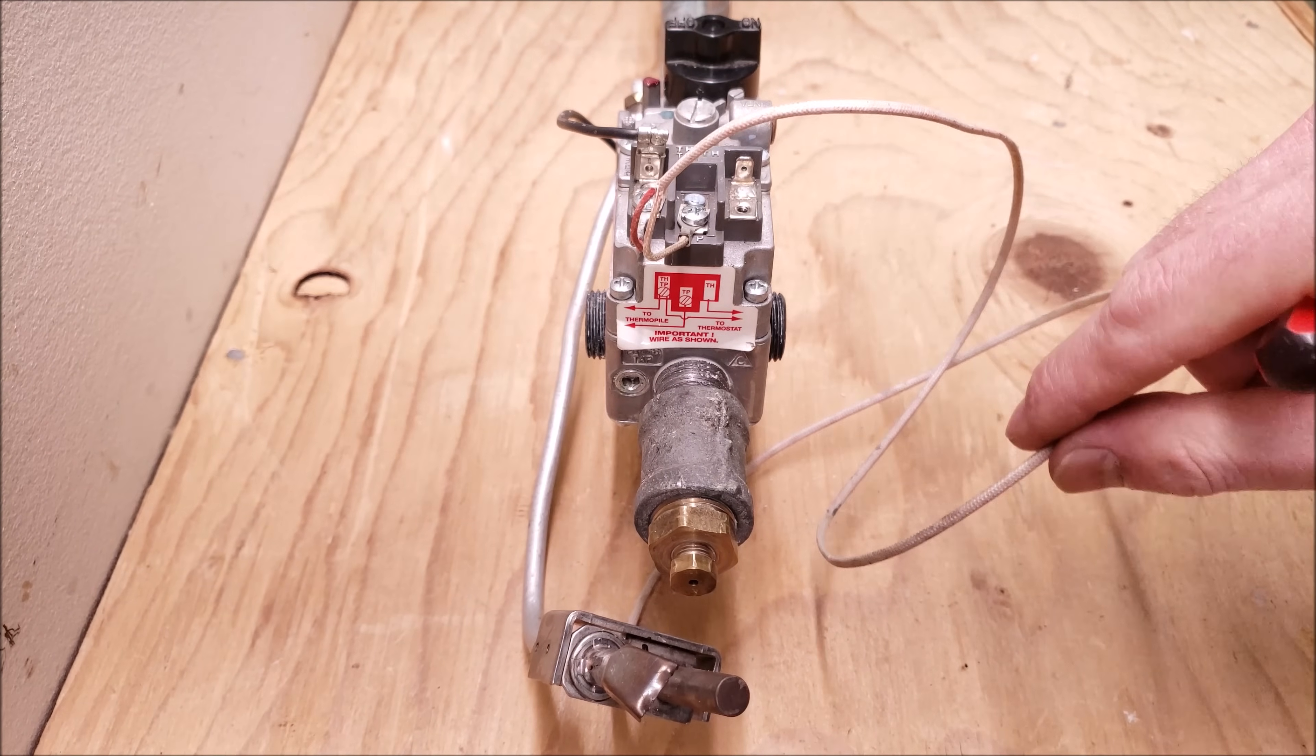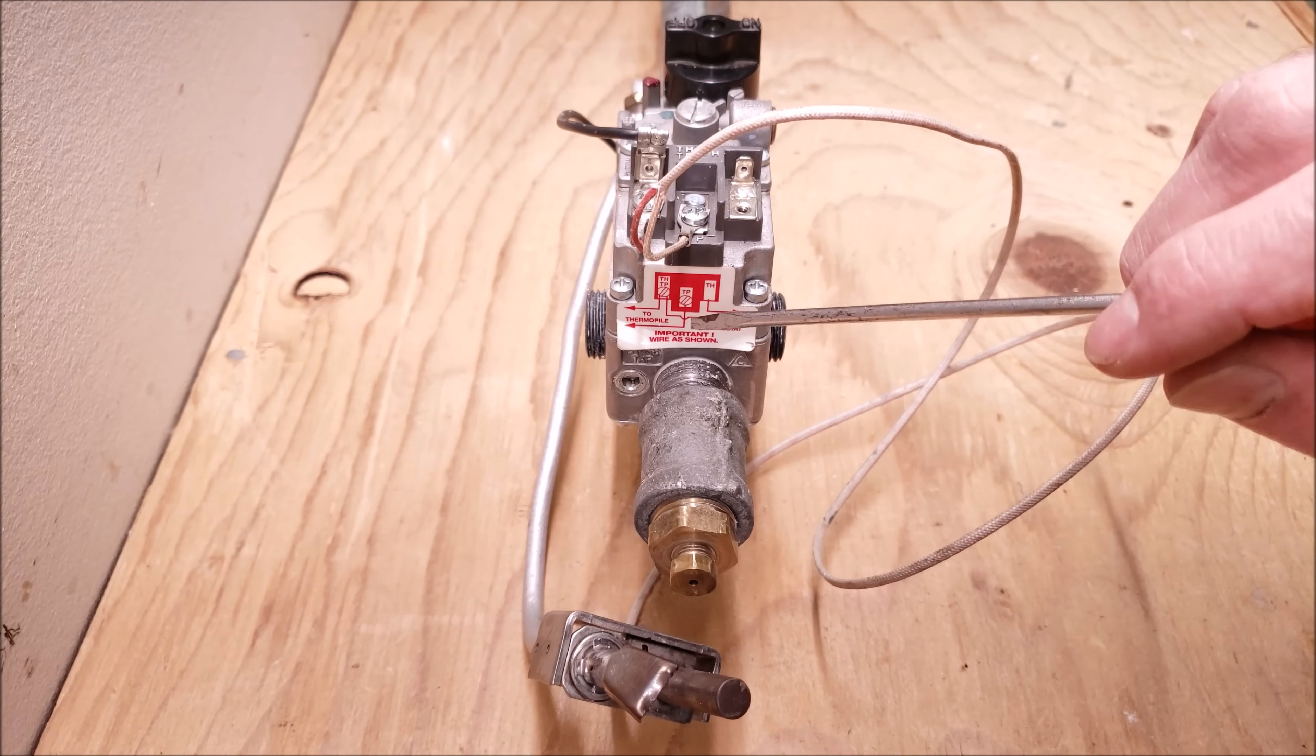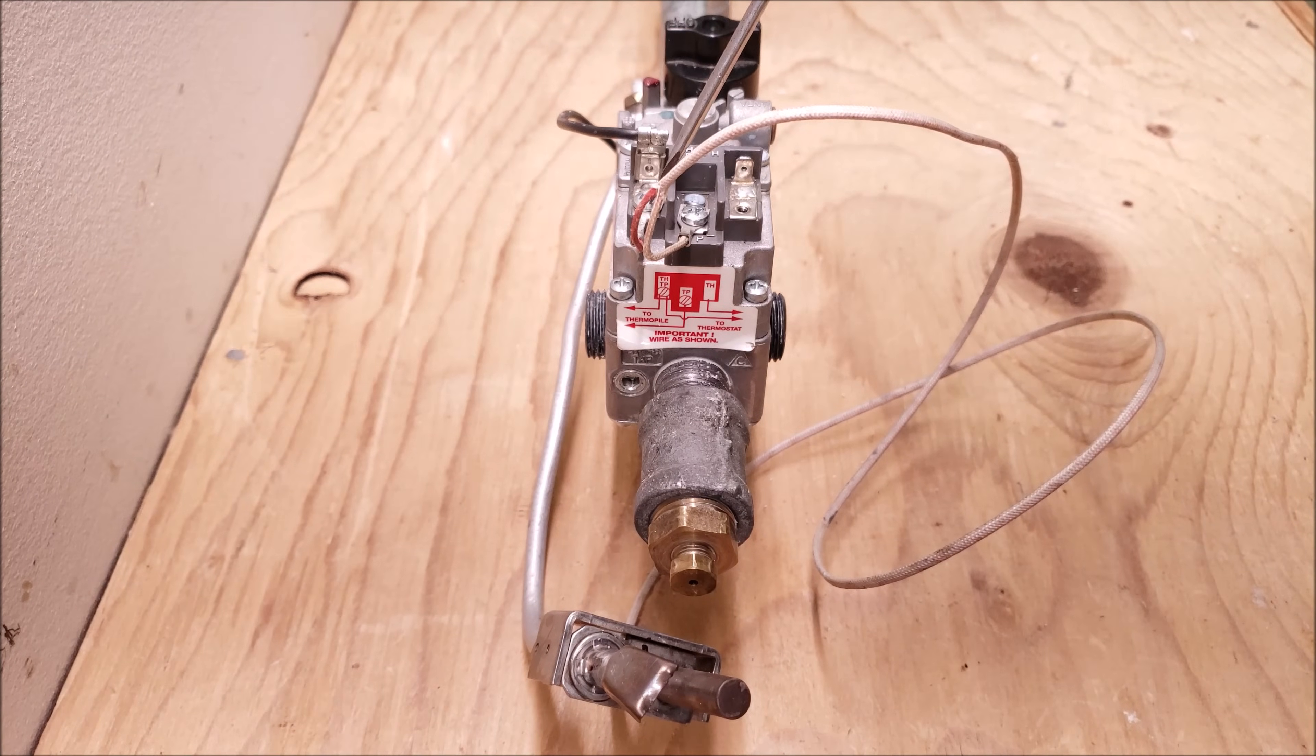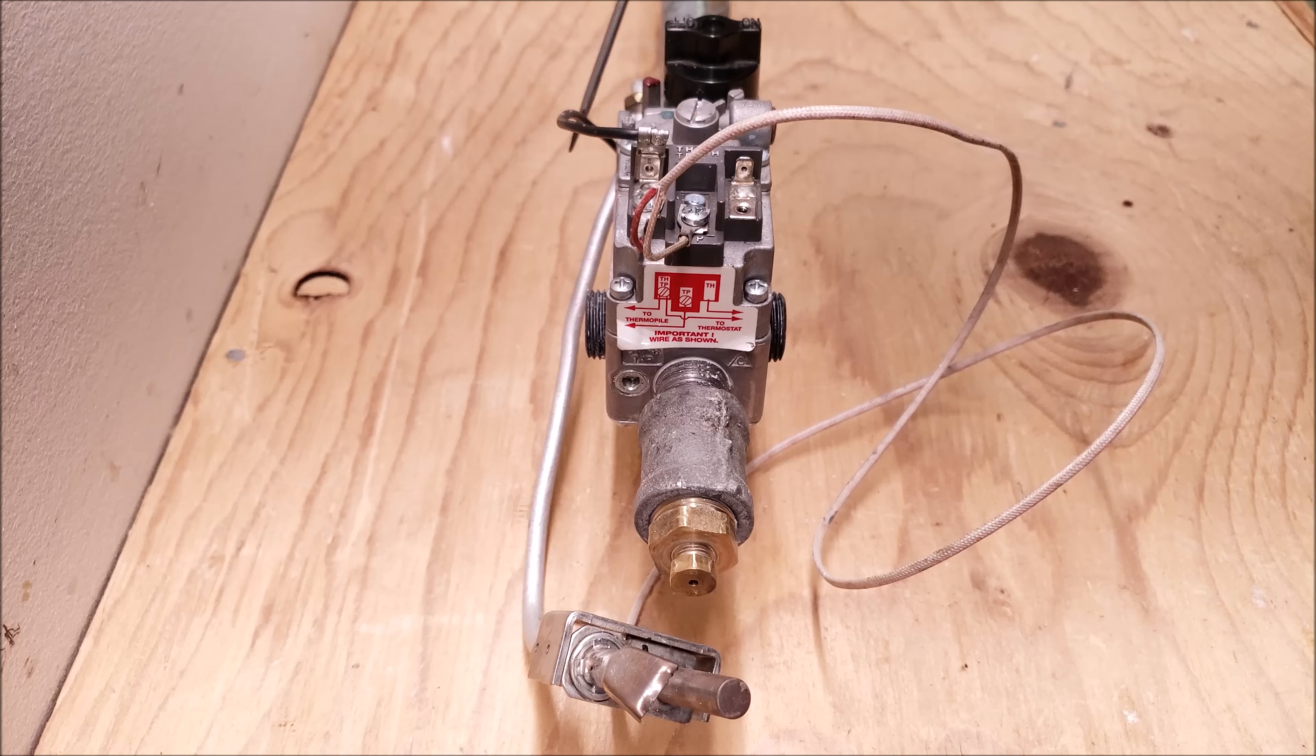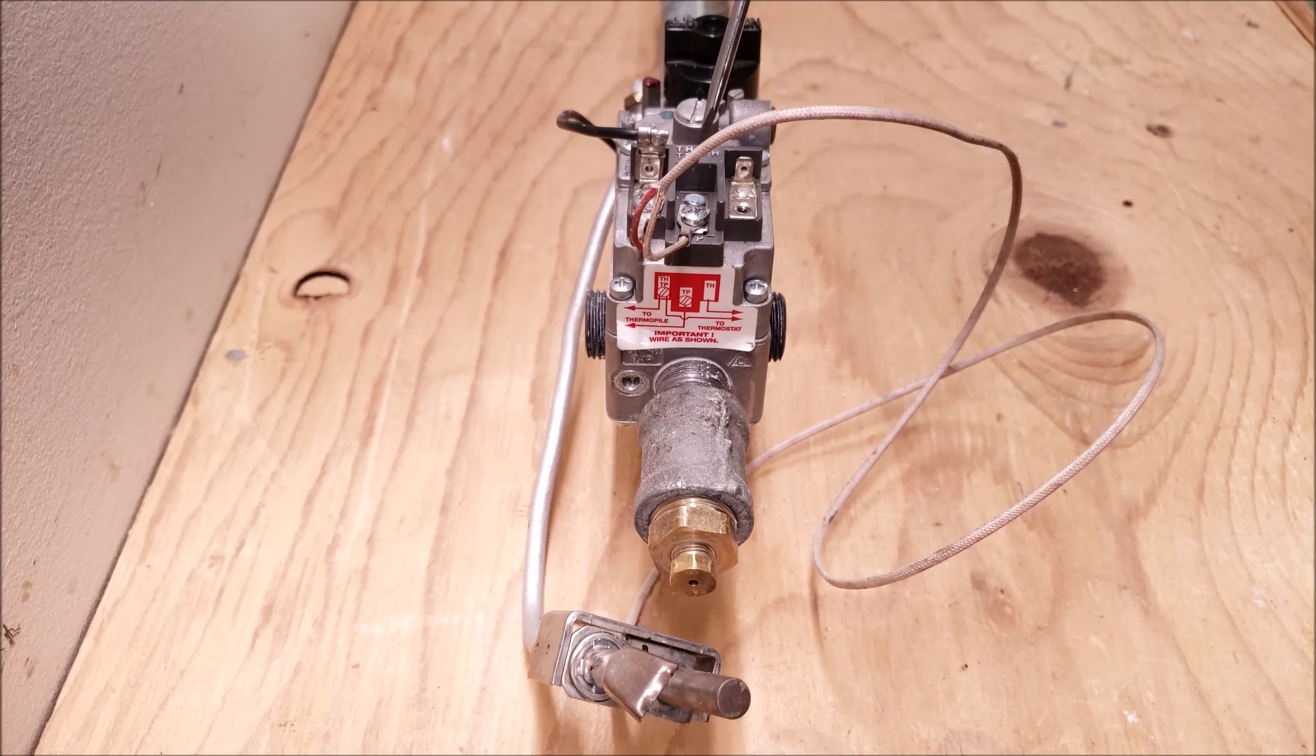So you see we have our thermopile actually wired into the gas valve and it's wired into the pilot solenoid valve. So we have our power coming into the THTP on the red wire right here and that gets connected to this wire and it runs over to the pilot solenoid and it finds its way back through the TP.